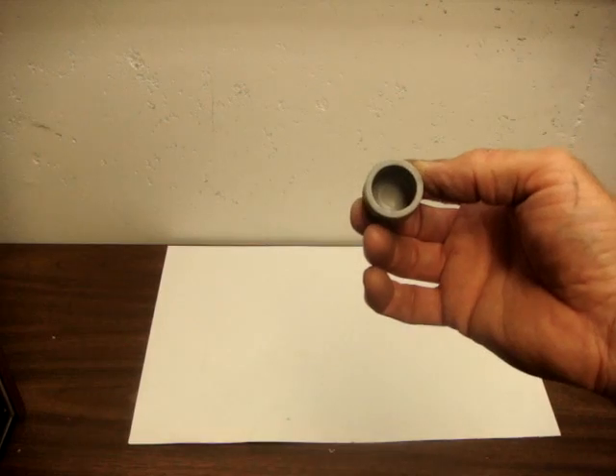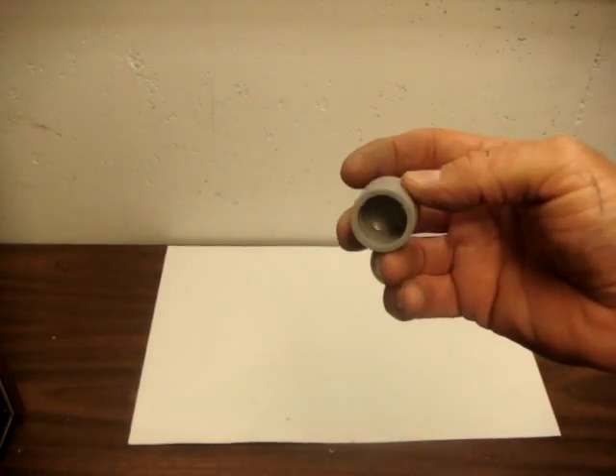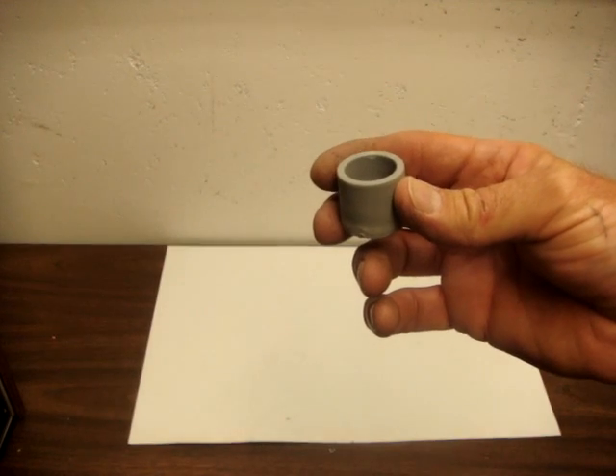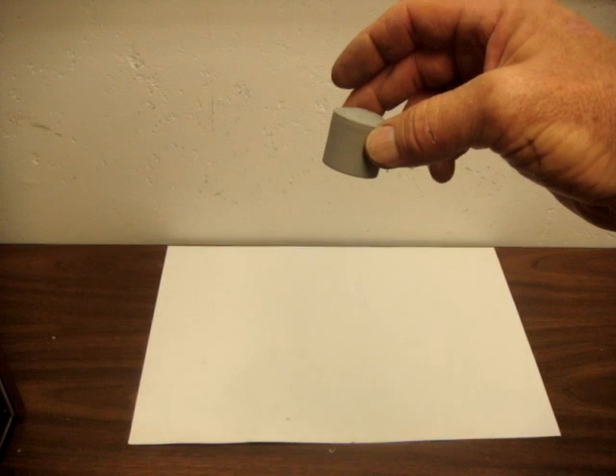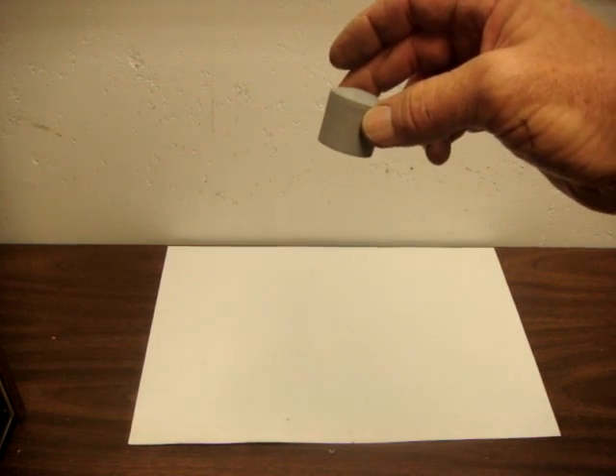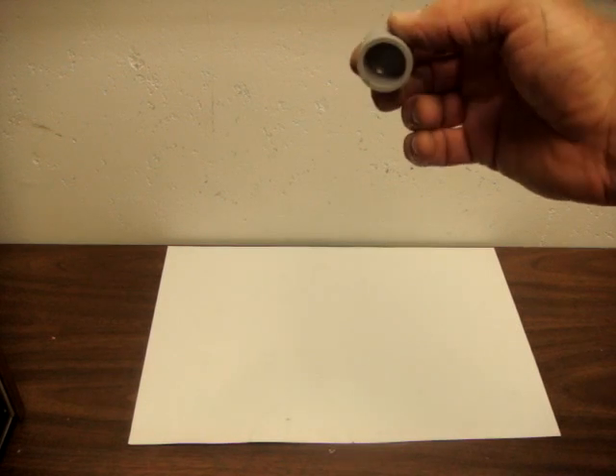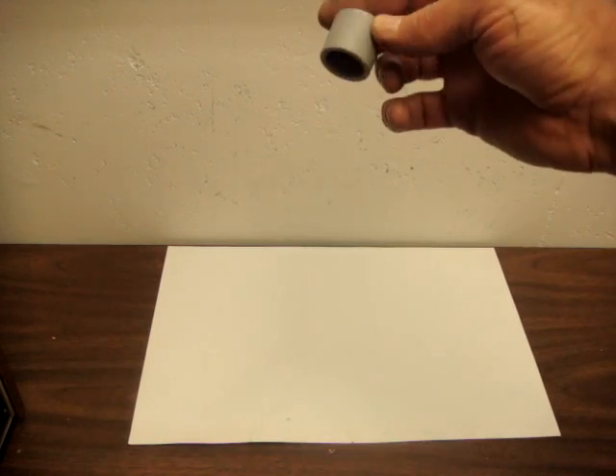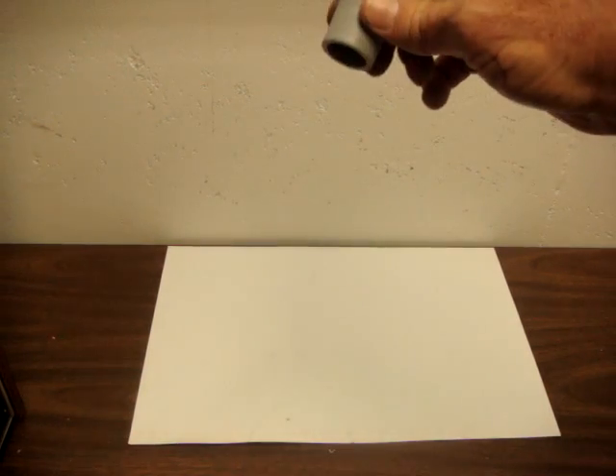This is a cap. This particular cap is PVC. This PVC cap is used with rough installations, usually outdoors, where there's a time lag between the installation of the conduit and the final installation of the wiring. By gluing caps on, people cannot contaminate the pipe with dirt, sticks, stones, concrete, sand, or other foreign materials.